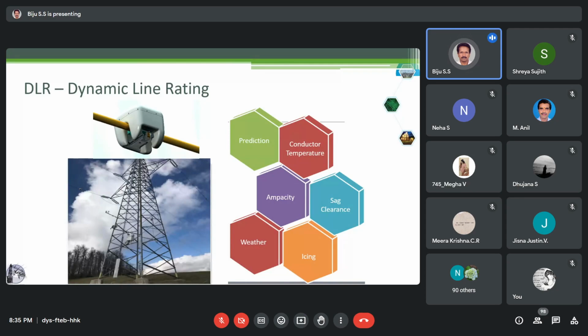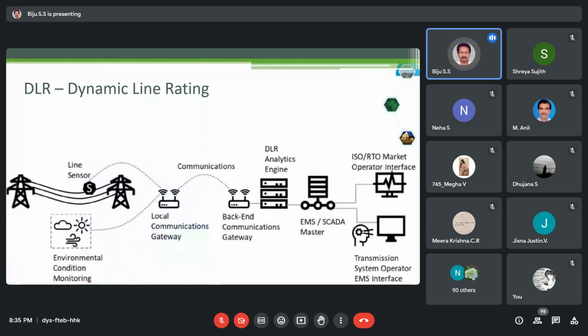Actually, we had done a DLR project in Kerala, and we found it increases the line rating of existing lines by around 20 to 30%. So this is the basic system of dynamic line rating. You have environment condition monitoring done here in the lines, the line sensors, and again there's a communication gateway. It can be 3G or basically a GSM network. Then you can have a backend communication gateway to the DLR analytics engine, which will be cloud-based, to do analytics of the whole system, and it will give information to the SCADA master, the SCADA system, saying that this can be your current loading. So that will be a big help for the system operator.